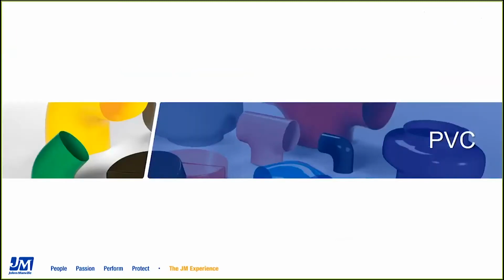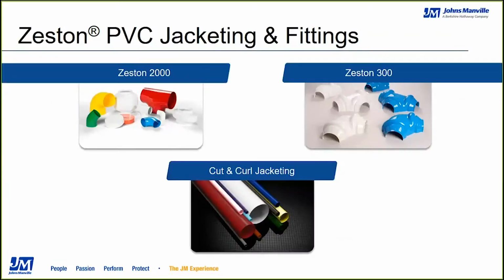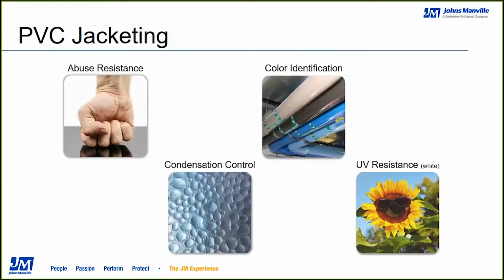PVC. We have several lines of the Zeston 2000 in white and color. You see the Zeston 300 in white and color, as well as cut and curl jacketing. PVC jacketing is typically used for abuse resistance. The colors can often be used for color identification, especially in mechanical rooms. This is a vapor barrier, so it is providing condensation control, and the white is UV stable.